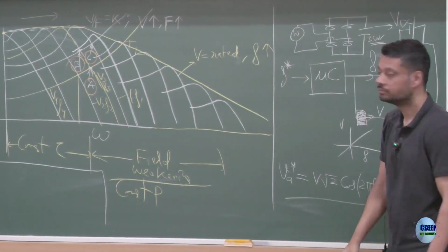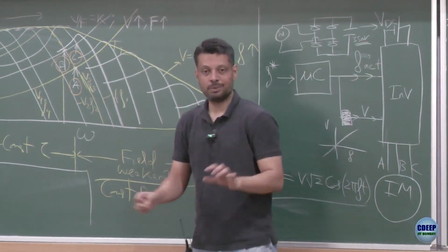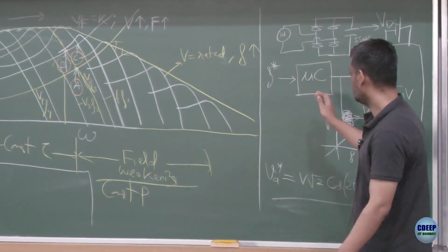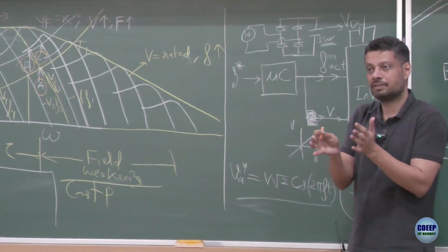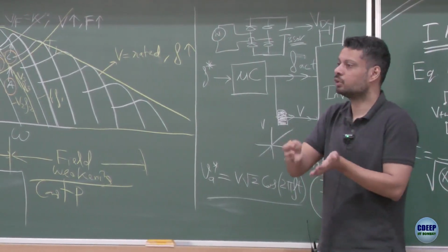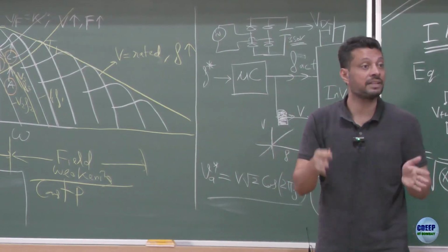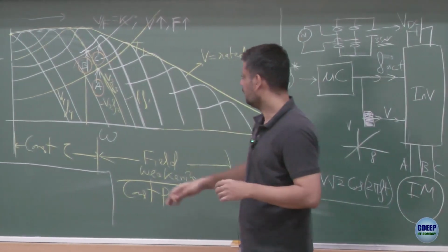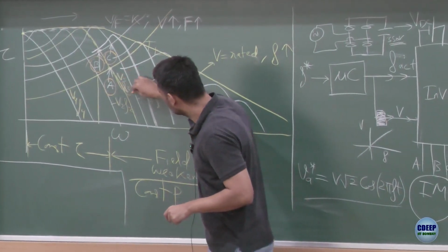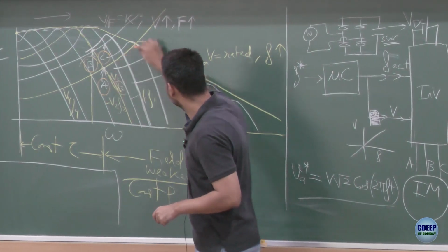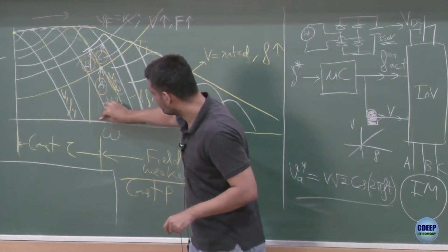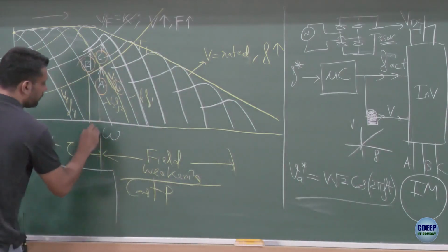Okay, look at point A, B and C. You can see it right from the back. Point A, B, C are visible. You have set a voltage and frequency on the console, right? It had its logic. The motor started slowly. The frequency initially was very low, and slowly the voltage and frequency increased, and it reached the frequency at which you have set the controller, 50 hertz or 45 hertz, whatever you have set. And now this is the F3 that you have set. You are operating at F3 and your load is this characteristics. So your point of operation is A.